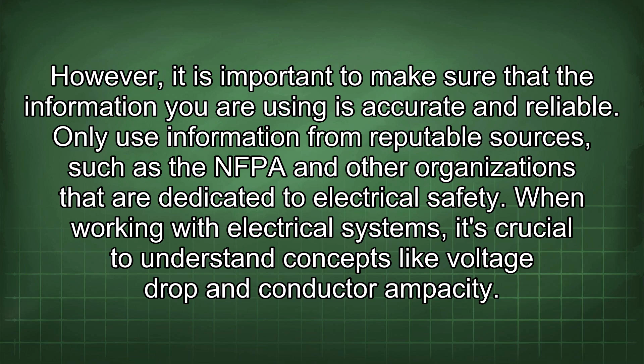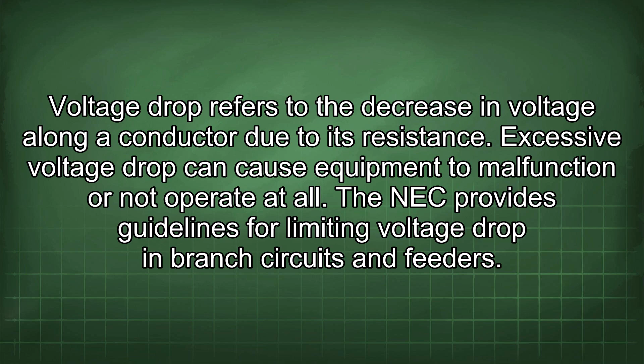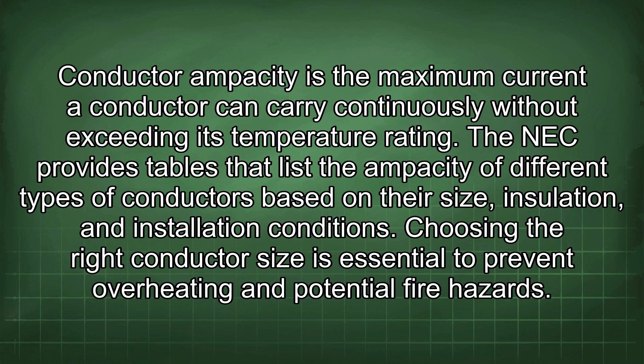When working with electrical systems, it's crucial to understand concepts like voltage drop and conductor ampacity. Voltage drop refers to the decrease in voltage along a conductor due to its resistance. Excessive voltage drop can cause equipment to malfunction or not operate at all. The NEC provides guidelines for limiting voltage drop in branch circuits and feeders. Conductor ampacity is the maximum current a conductor can carry continuously without exceeding its temperature rating. The NEC provides tables that list the ampacity of different types of conductors based on their size, insulation, and installation conditions. Choosing the right conductor size is essential to prevent overheating and potential fire hazards.